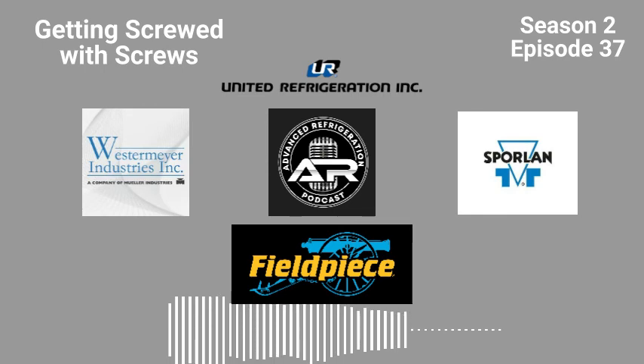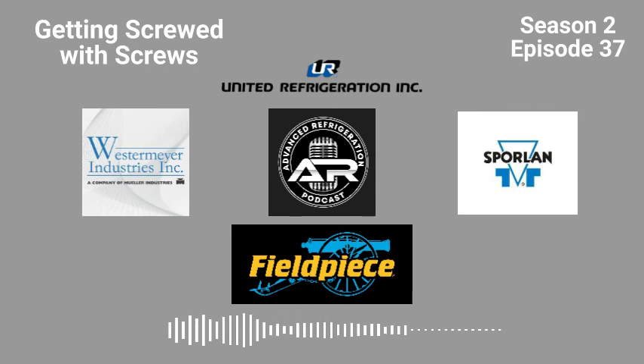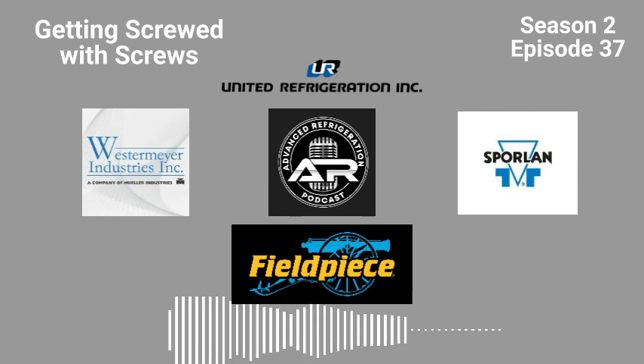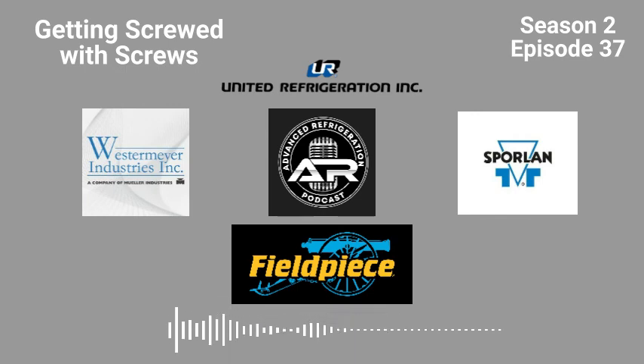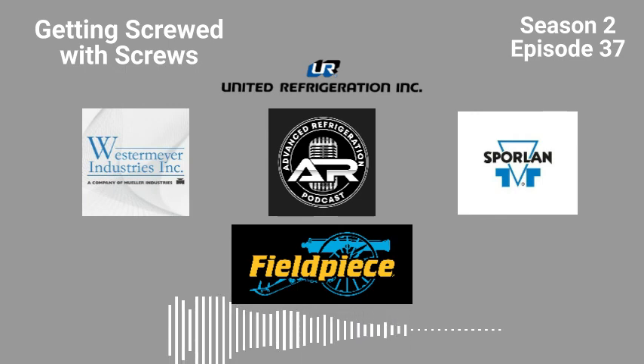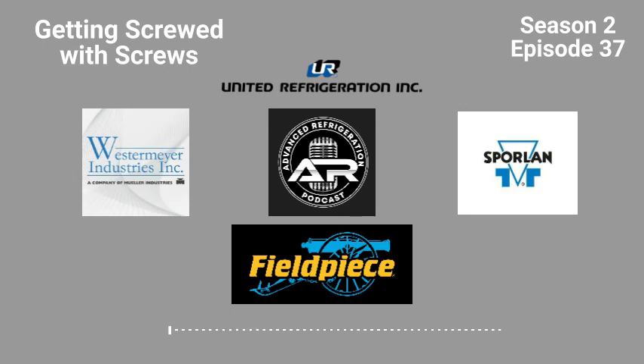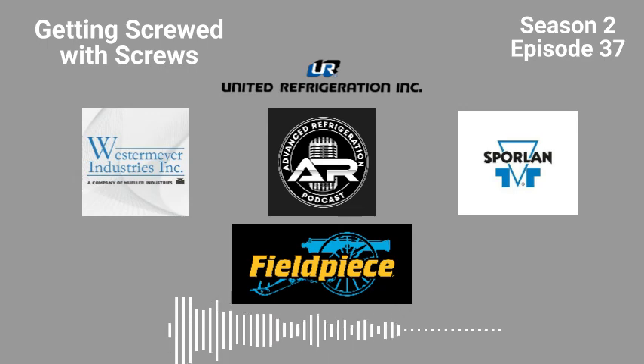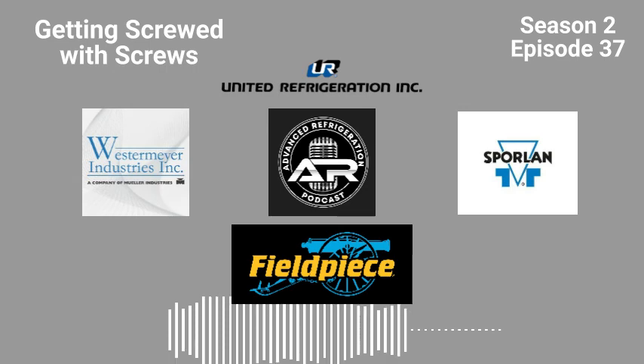To be honest, the last 10 startups have been absolutely rough. Is it because of the supply chain shit? Oh yeah, it's gotten way worse. Everything is just halfway put together, missing IOU tags. All these people are getting people from temp agencies to put this stuff together, and it's just horrendous. We had coils you couldn't even get transducers on. You physically could not fit the transducer where they put the packed angle valve. I've seen a bunch of pictures just today. I can't even tell you the amount of coils where we've had to move all these transducers because you can't get them on the packed angle valves.